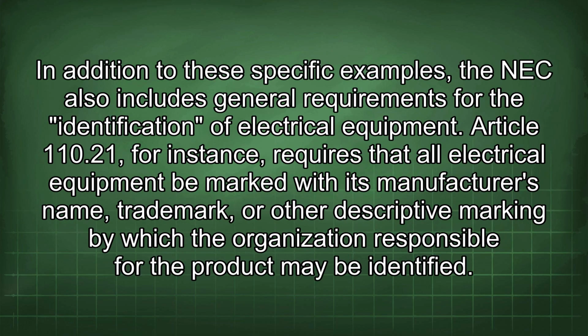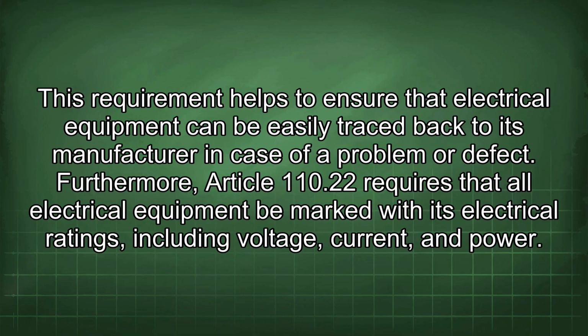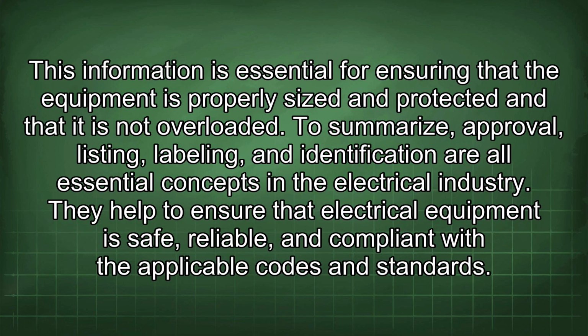In addition to these specific examples, the NEC also includes general requirements for the identification of electrical equipment. Article 110.21, for instance, requires that all electrical equipment be marked with its manufacturer's name, trademark, or other descriptive marking by which the organization responsible for the product may be identified. This requirement helps to ensure that electrical equipment can be easily traced back to its manufacturer in case of a problem or defect. Furthermore, Article 110.22 requires that all electrical equipment be marked with its electrical ratings, including voltage, current, and power.